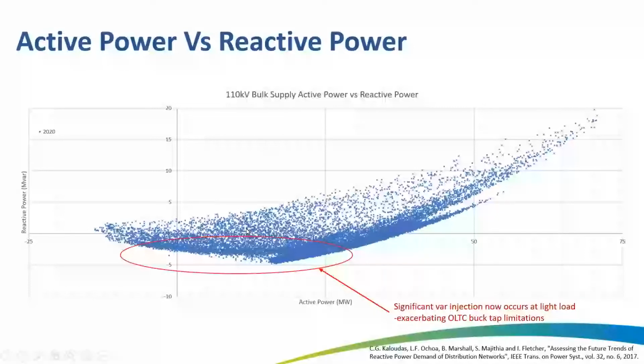So just to contrast this data from 2020, yes, that's one other point, sorry, I wanted to highlight here was the reactive compensation. You can see that as a result of that, reactive compensation is actually mitigating some of those capacitive flows when we do have the reverse flows, and that's those solar inverters contributing.